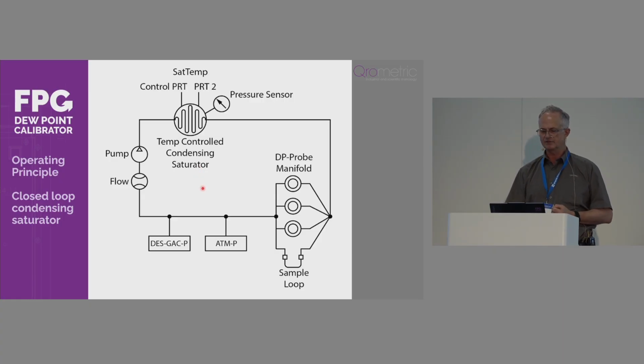And of course, there are practical things required. So we have a circulation pump, flow measurement. We have a purge function for cleaning or over-drying the system if we need to. And we can also introduce more water into the system with an atmospheric purge. And then here we have the practical point. We have 3 sensor connection points. And we have a sample loop where you can connect to any type of analyzer using a Swagelok or similar kind of connection. So very, very simple in concept, but quite complicated in practice because you're working at ppb levels in some cases, so you have to seal it very carefully.